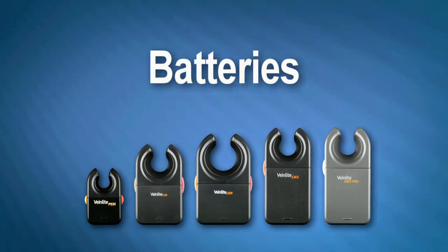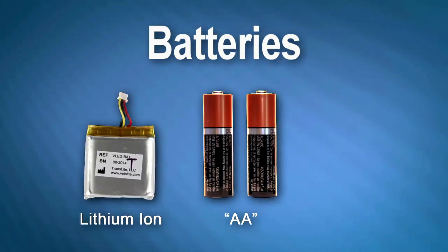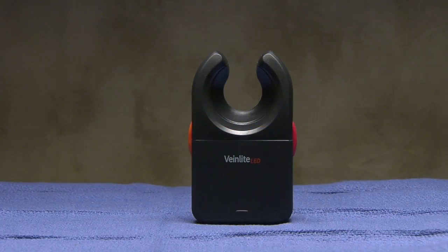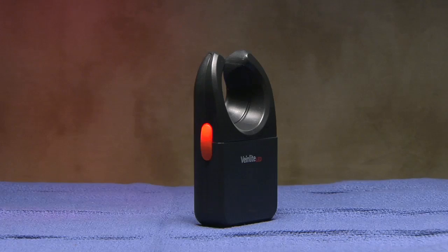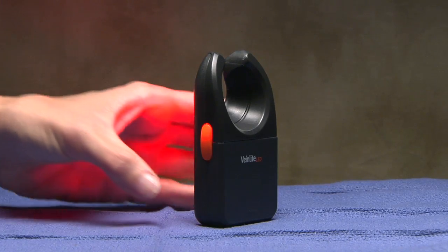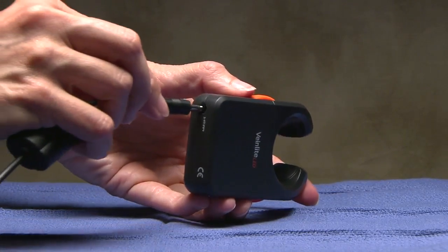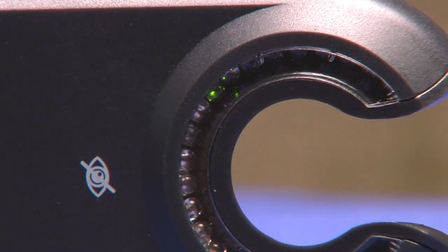The Veinlite family of products are powered by either rechargeable lithium ion batteries or replaceable AA or CR2 batteries. Certain devices are equipped with a low battery level indicator light, which will illuminate when the battery charge level has dropped to approximately 20% of the full battery charge. If your device uses the rechargeable lithium ion battery, use the supplied charger to return the battery to full strength. A red LED can be seen through the clear window when charging, and a green LED can be seen when the battery is fully charged.